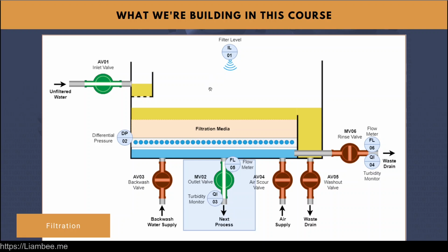So now we can start bundling stuff down into single booleans for interlocks, rather than us checking every single time that we need to check, is everything for this sequence okay? We can start grouping that stuff together in an interlock manager, and that interlock manager takes in all of the data that we need, or accesses all of the data that we need to access, and amalgamates everything down into a single interlock.